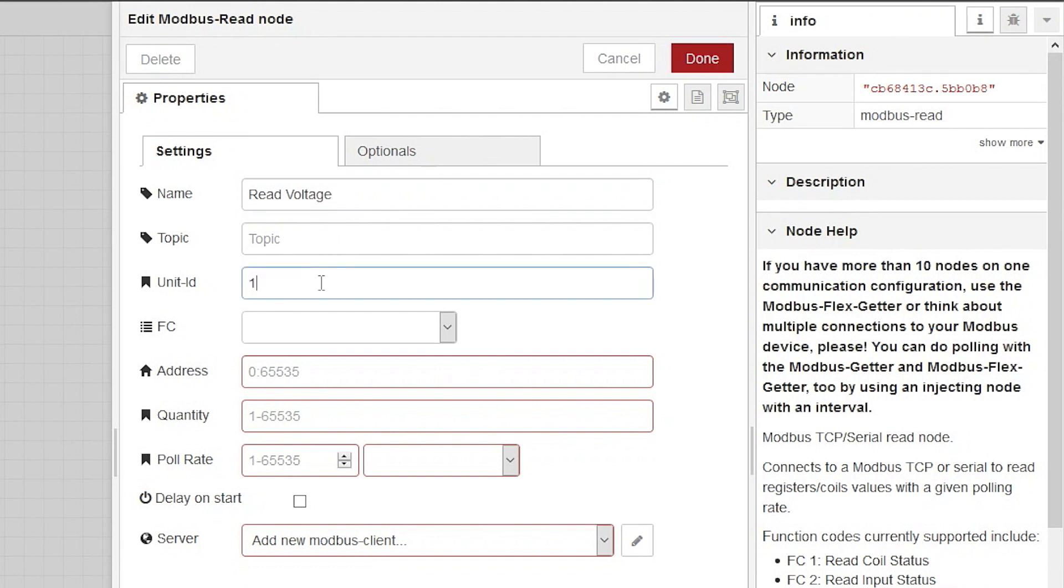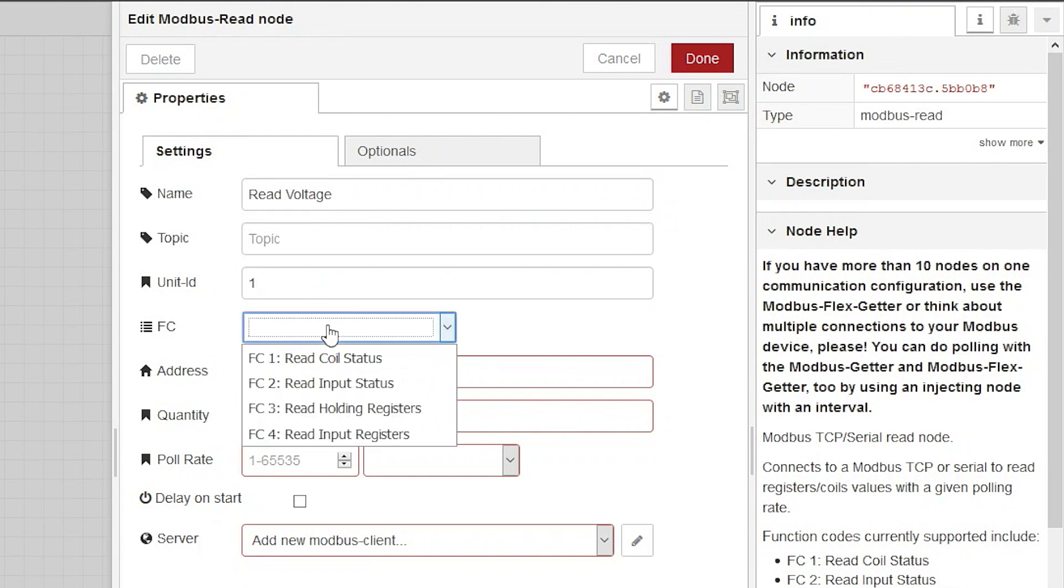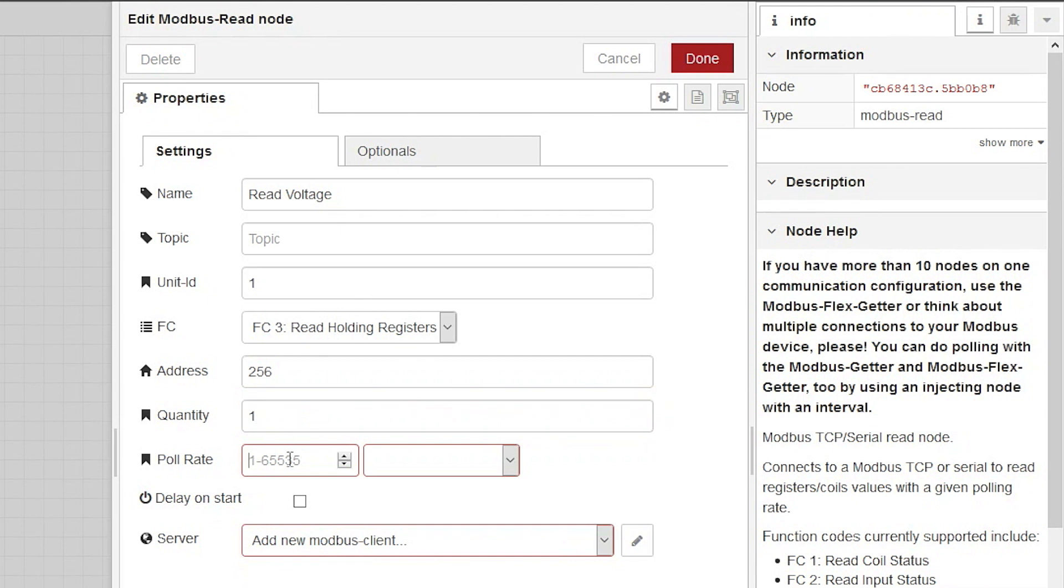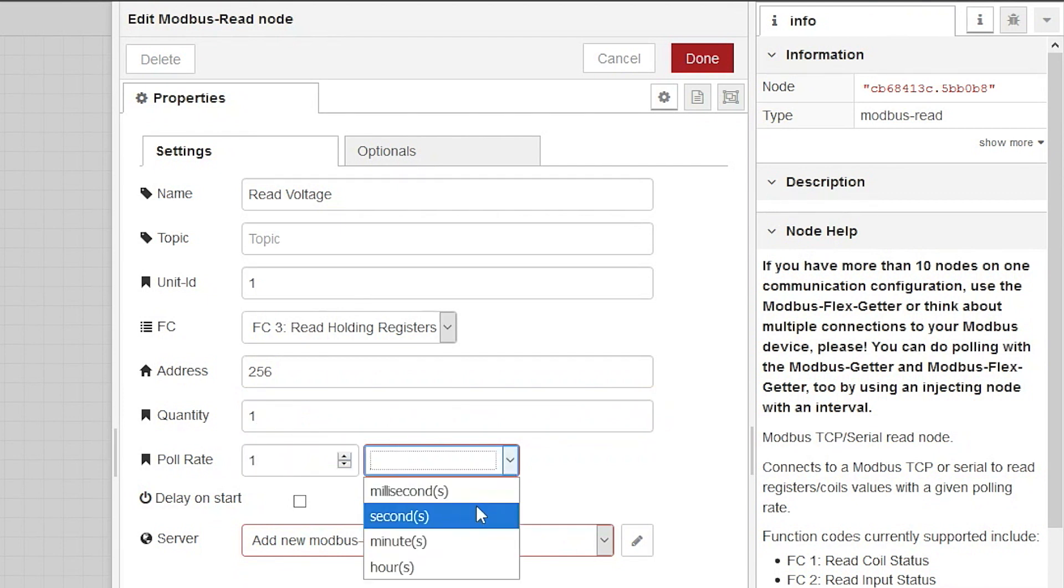The device ID is usually 1, but it is set up in your Modbus device along with its IP address, so in your case it might be something different. We're going to be reading a holding register with an address of 256. It's a single 16 bit integer. Let's set a poll rate of once per second.